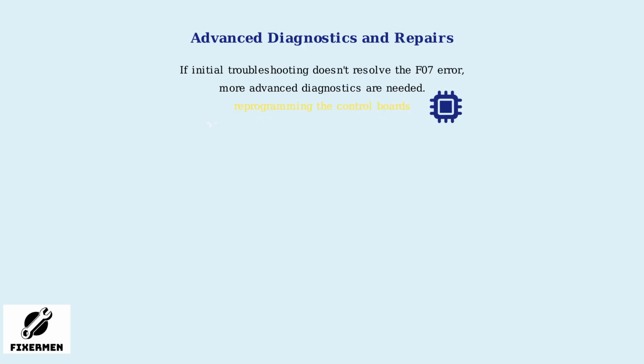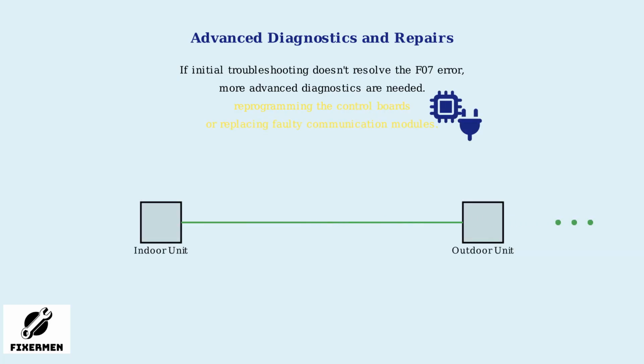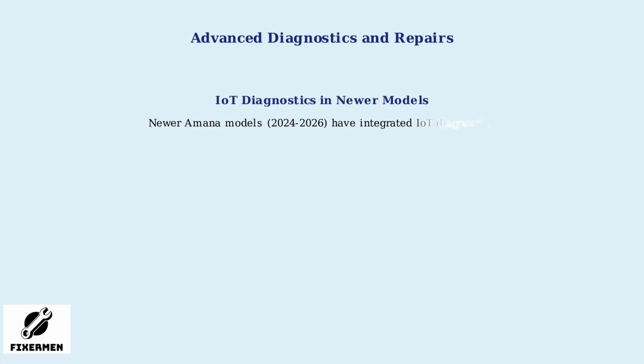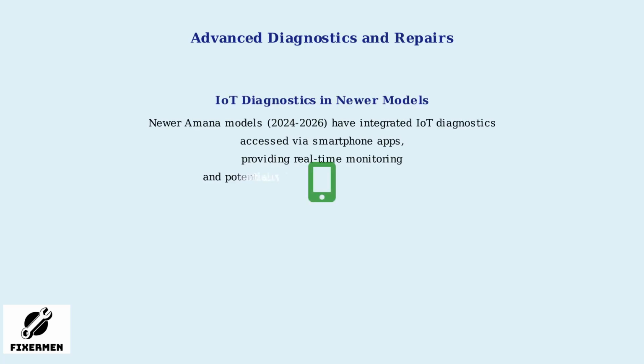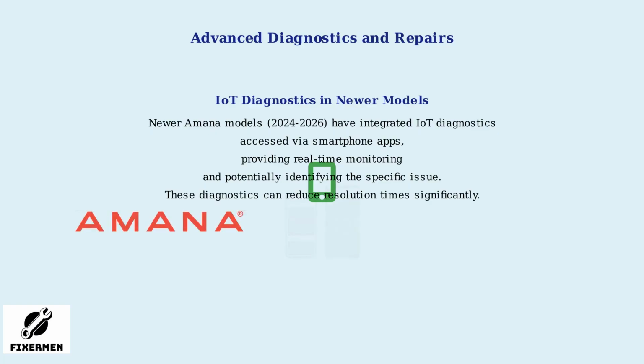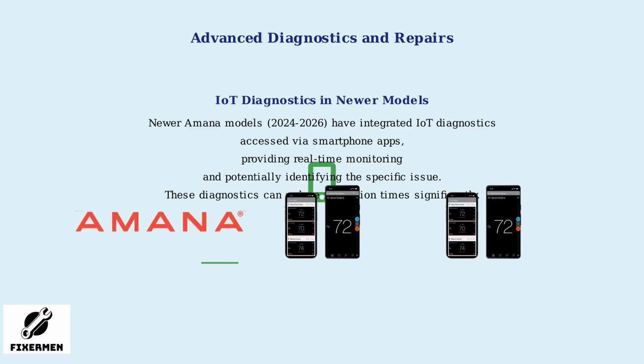If the initial steps don't resolve the F07 error, more advanced diagnostics are needed. This might involve reprogramming the control boards or replacing faulty communication modules. Newer Amana models from 2024 to 2026 have integrated IoT diagnostics that can be accessed via smartphone apps, providing real-time monitoring and potentially identifying the specific issue. These diagnostics can reduce resolution times significantly.